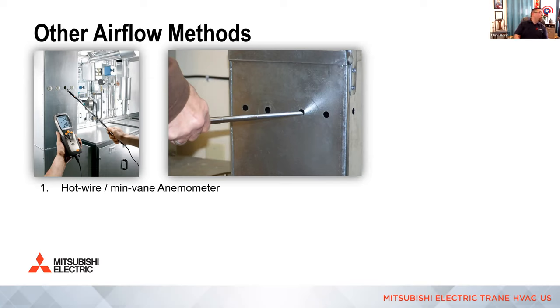Now, I don't have the manual offhand. There's an ANSI/ACCA manual that just came out for quality of HVAC installation and grading. If you're an energy rater, you probably know what I'm talking about right offhand. It's probably the first time three or four organizations actually agreed on a process. And they walk through grading duct systems, and you would measure temperature, static pressure, and measure volume of air in order to grade that duct system versus what the design was, right? It needs to be within a certain percentage of what the design is.